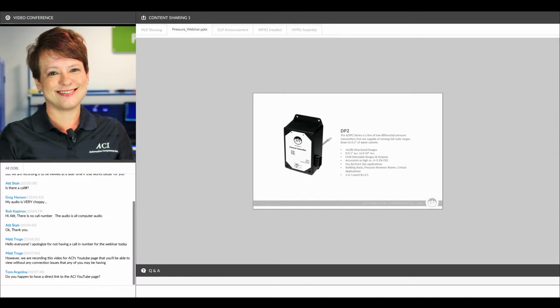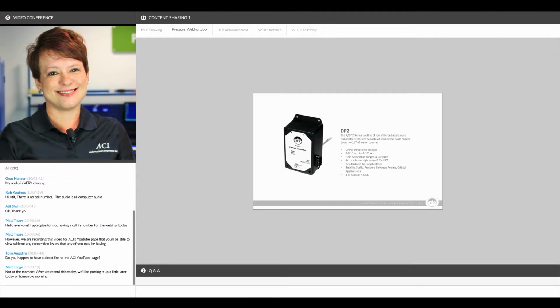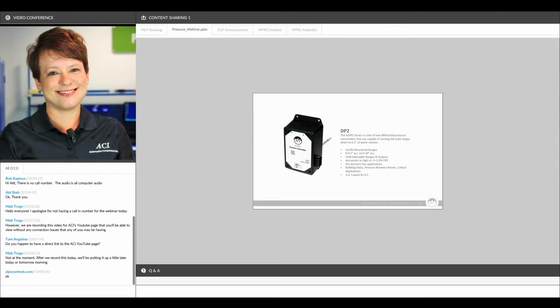This one is sold primarily for critical applications like building static, pressure between rooms, filter pressure drop, and clean rooms, because you are going to get accuracies on this unit that are as high as plus or minus 0.3% of full scale. So it's pretty darn close to a laboratory grade device at a fraction of the cost. It's also available with or without an integrated pitot tube.